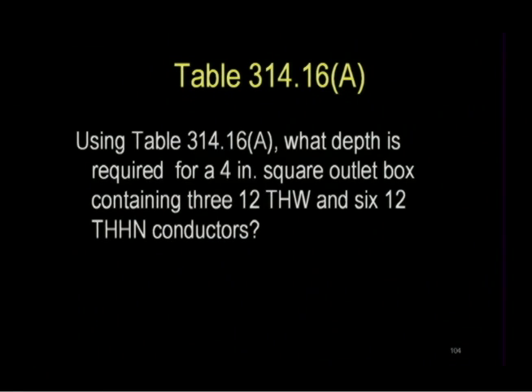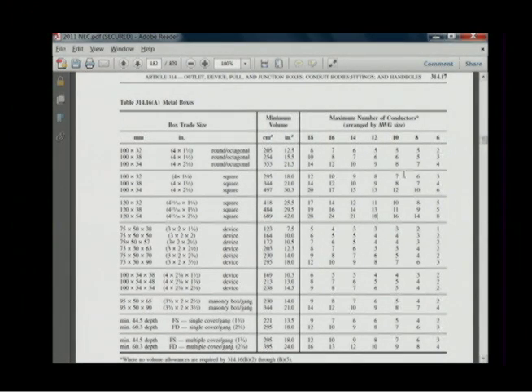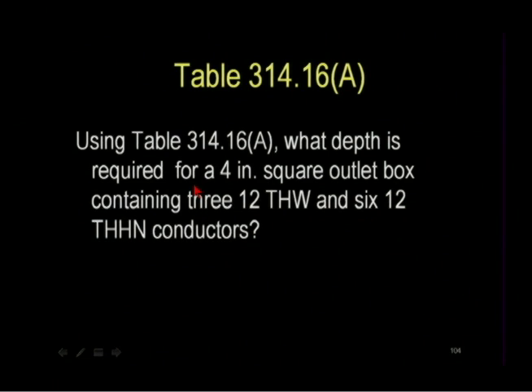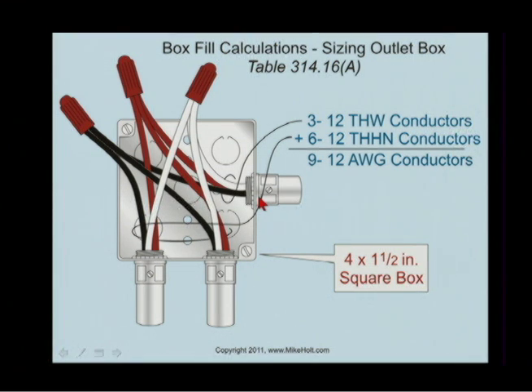Table 314.16(A). Using the table, what depth is required for a 4 inch square outlet box containing three 12 THW and six 12 THHN conductors? So that's nine 12s. It would be inch and a half deep box, right? The key here to the question... the insulation didn't matter. Exactly. It doesn't matter what insulated conductors you have. It's just simply you had 12 gauge wire. It could have been bare. We don't really care. And here's that example. Three 12s and six 12s. It's nine 12s. Table 314.16(A) would say a 4 square by 1 1/2 inch deep box would be sufficient for that.